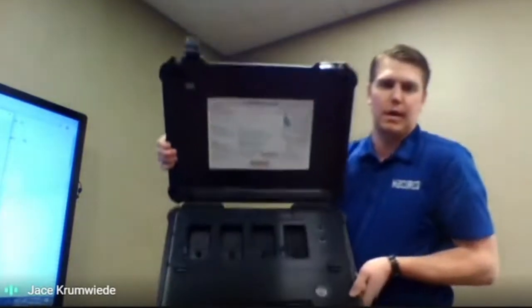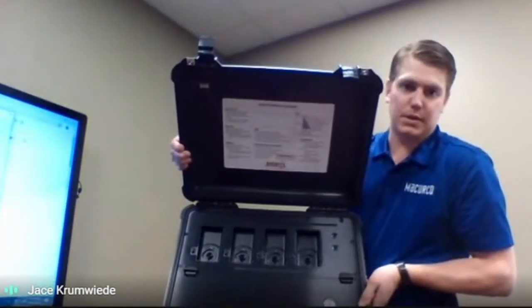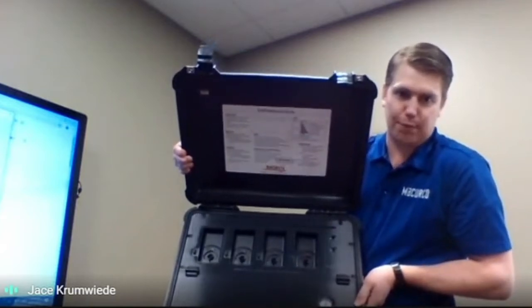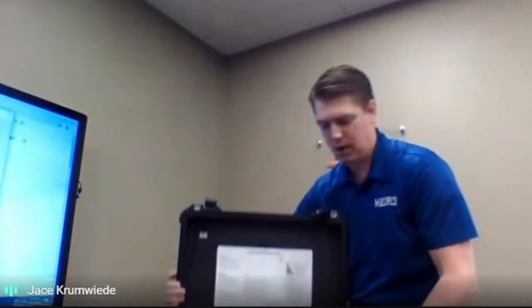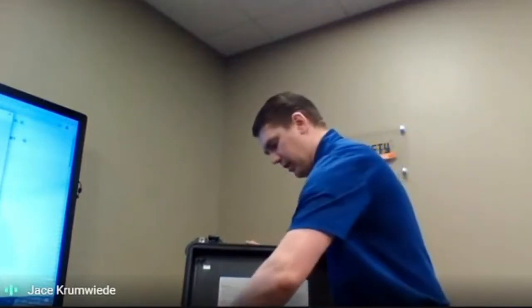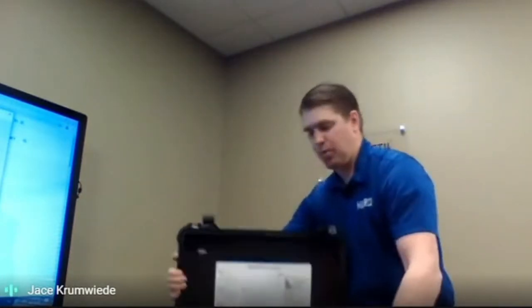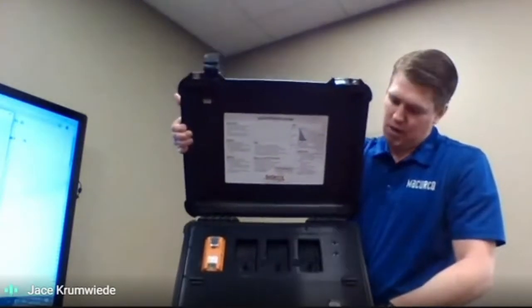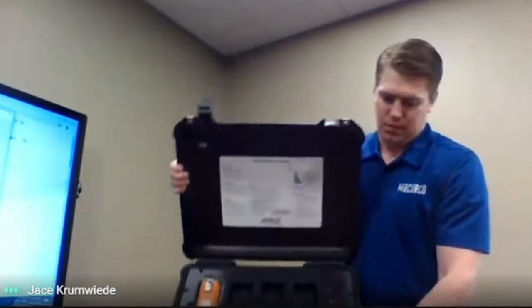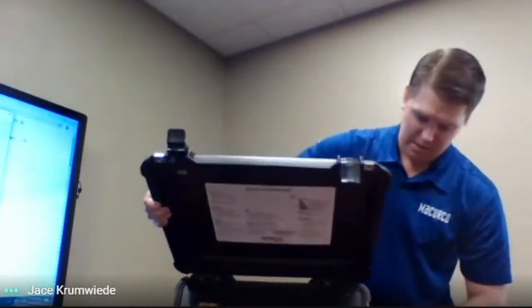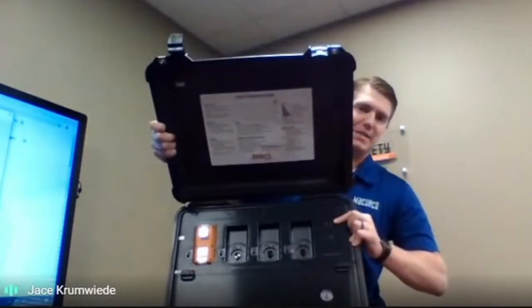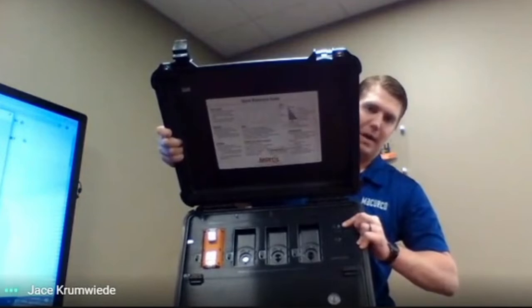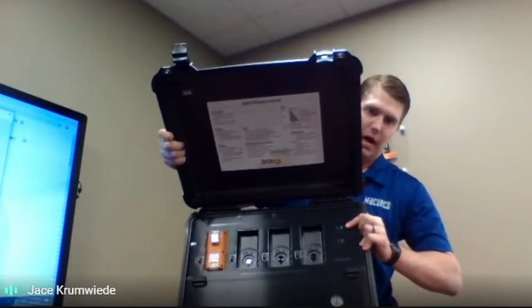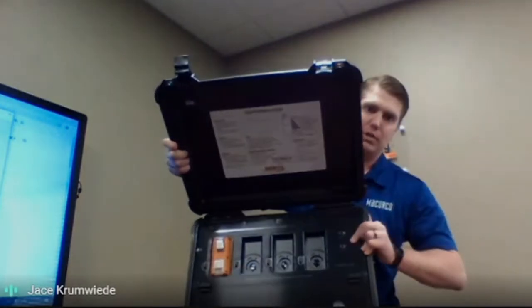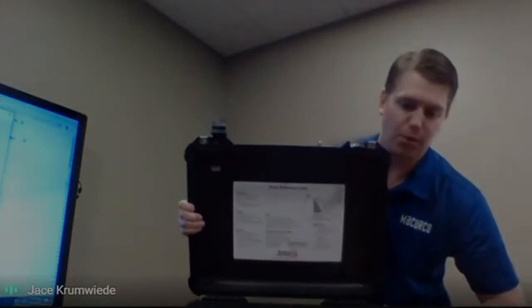Open that thing up, and what you'll see is 4 bays. Now the single gas and the multi-gas station is the same setup, it's just a different form factor, but you're going to see those bays will accept up to 4 monitors. What I do is I press that in there, and you'll see it sticks, and then you'll have 2 buttons here. One for your bump testing, so it's going to do an automatic bump test on it, and it will indicate whether it passes or fails, and then the next one would be for doing an actual calibration. So bump test and or calibrate up to 4 units at a time.